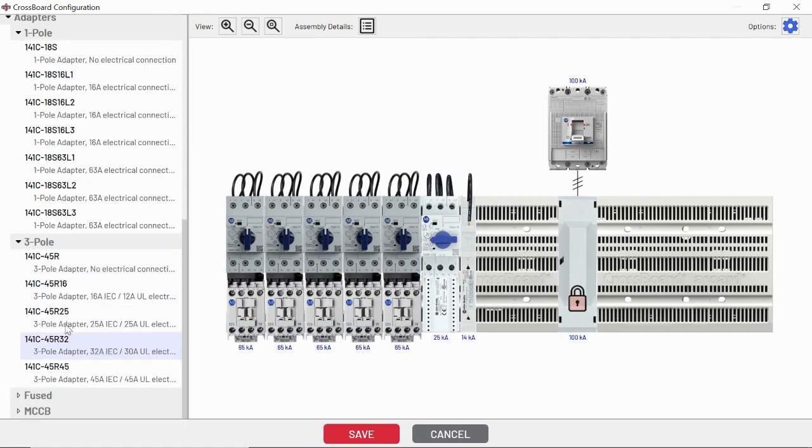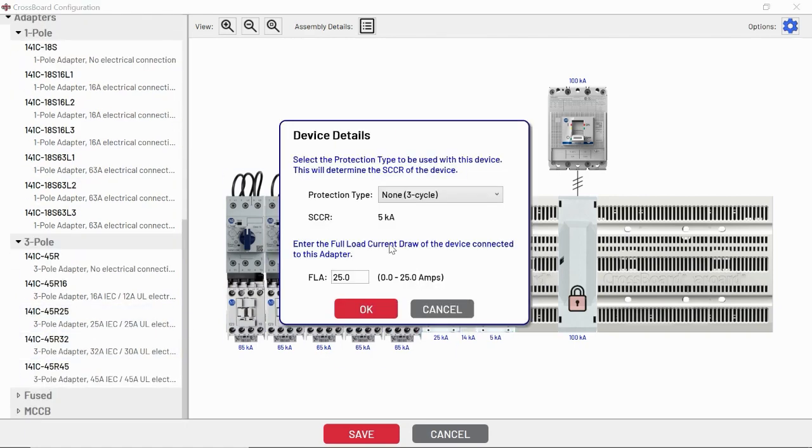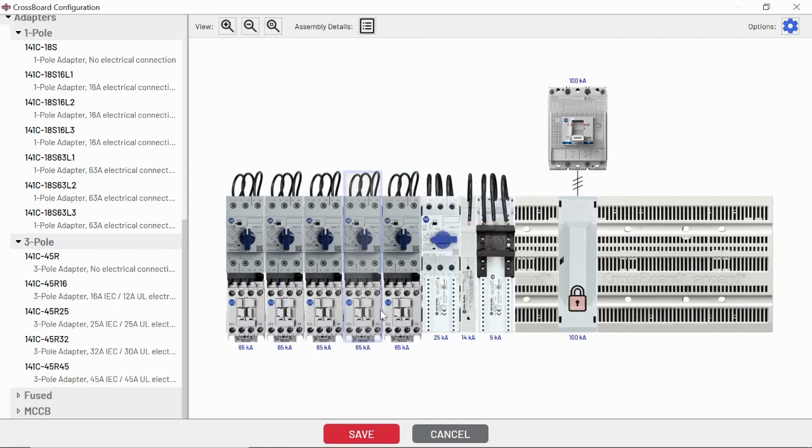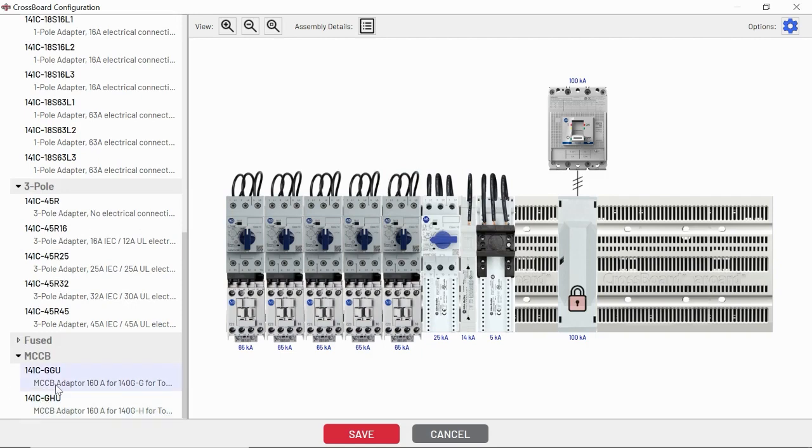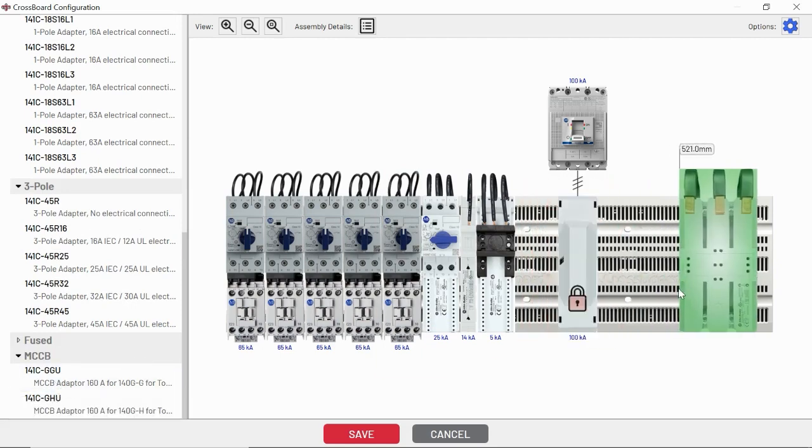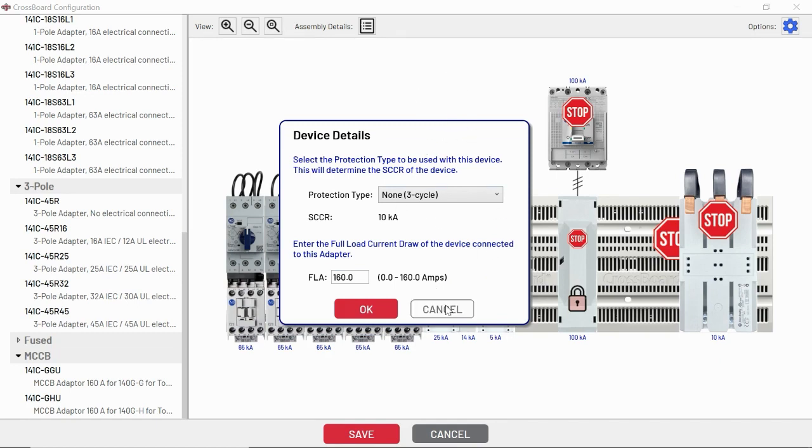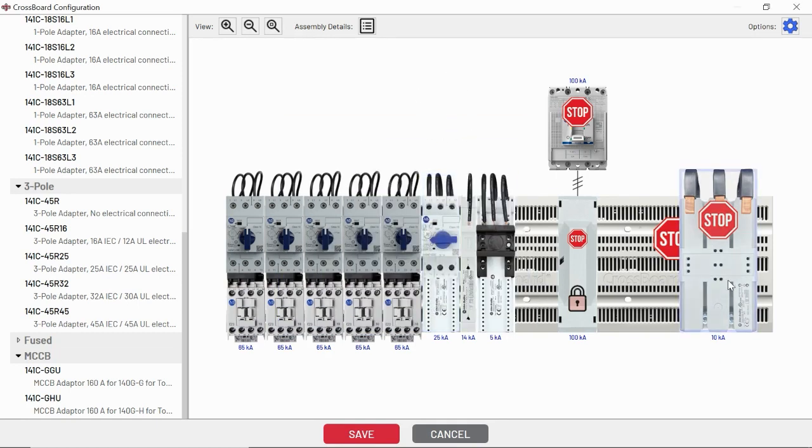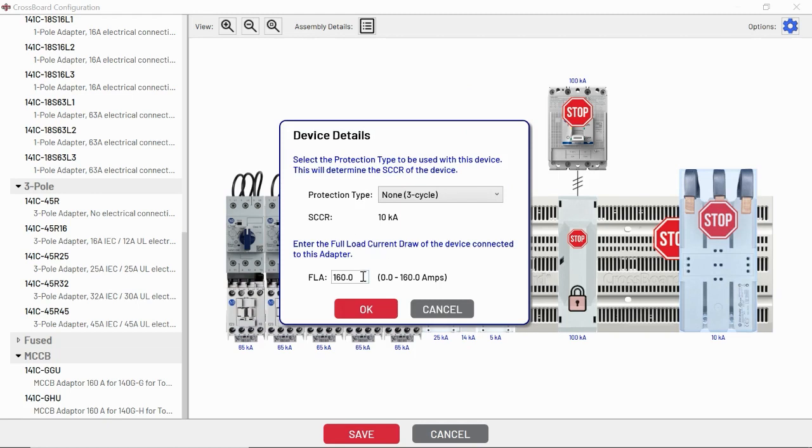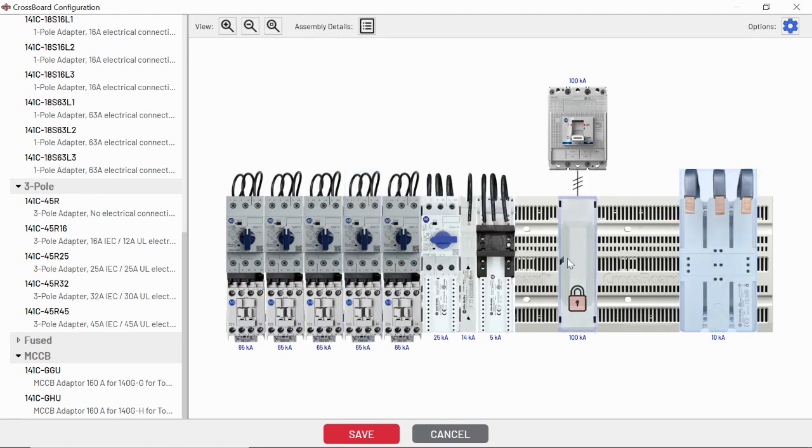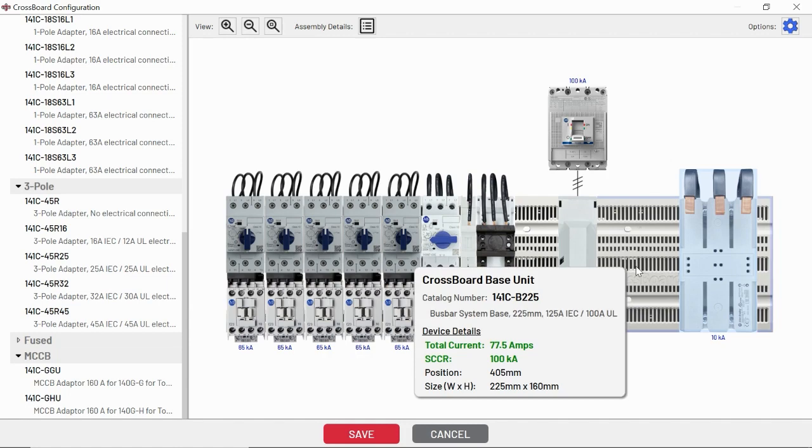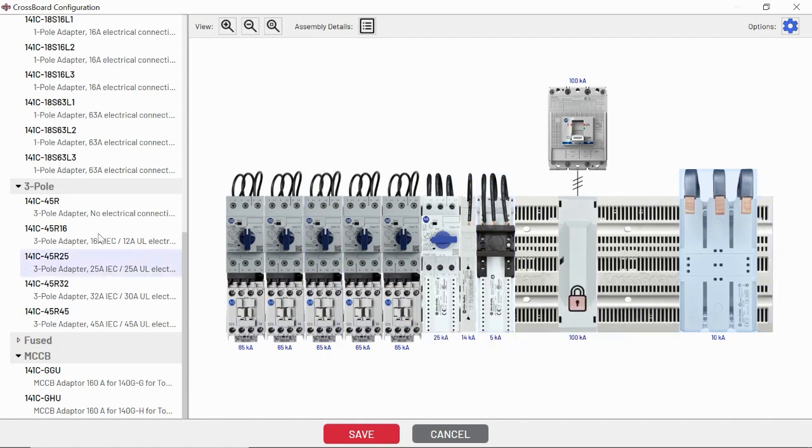You've got one pole options. You've got three pole options as well. Let's say that we went over our current on here. You'll see that it's going to warn you and says, hey, we're above the maximum allowed current for the IEC standard that we selected here. It's going to give you a big warning. If we adjusted that back down under the limit, you'll see that goes away.